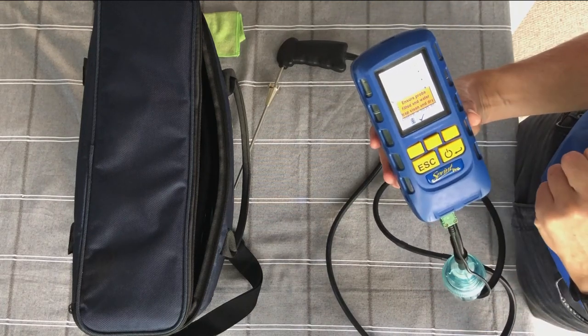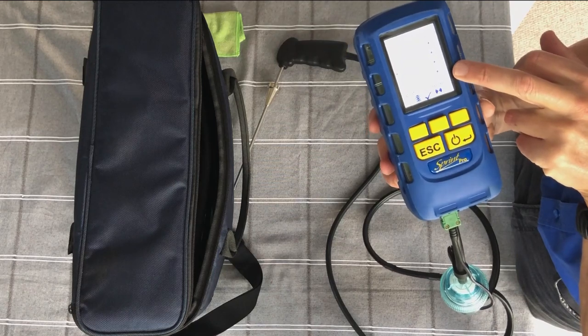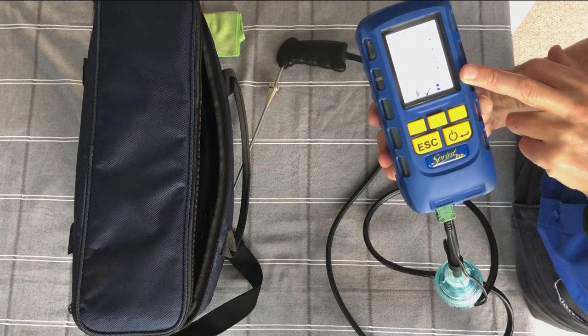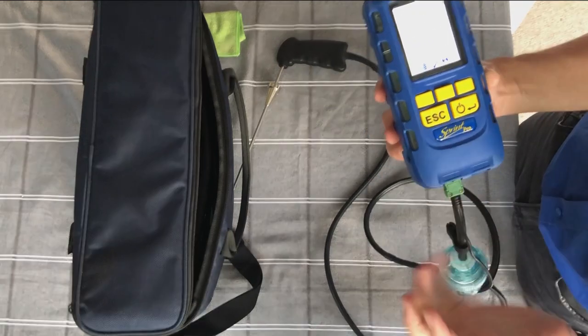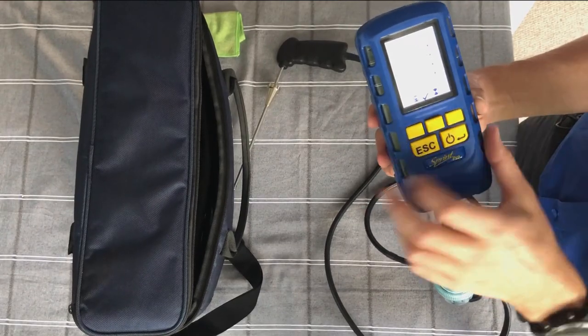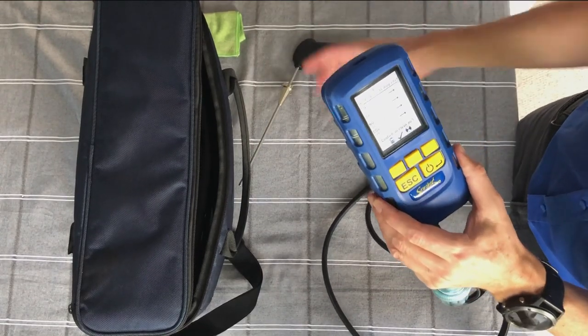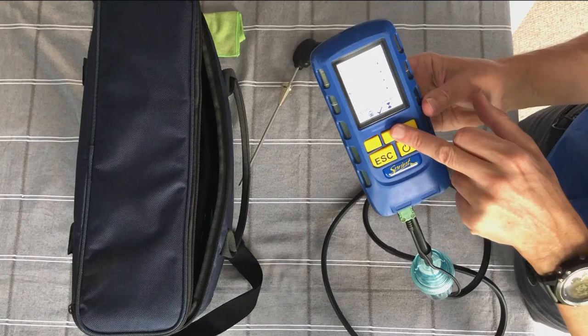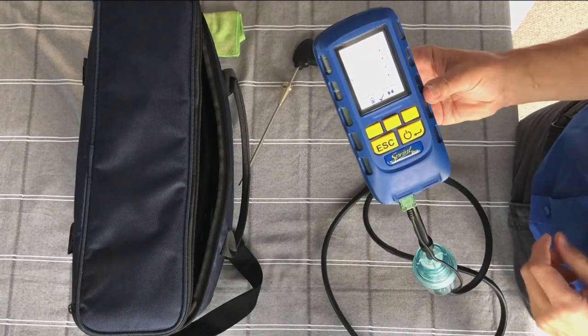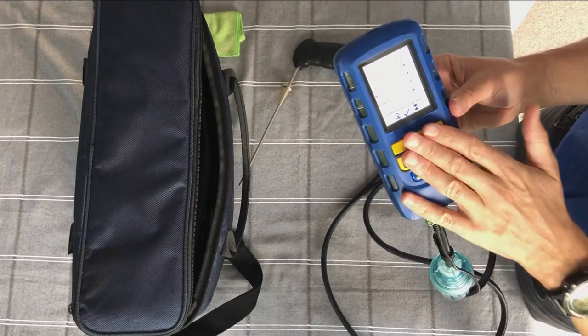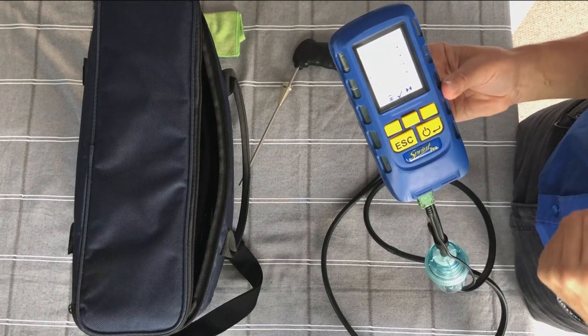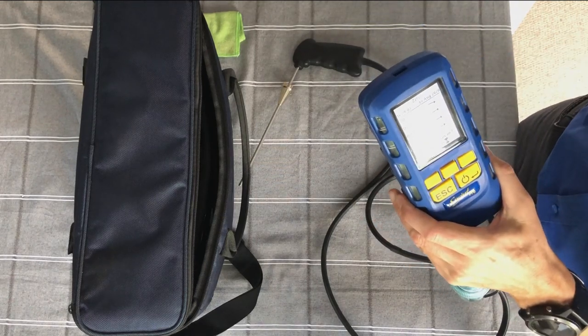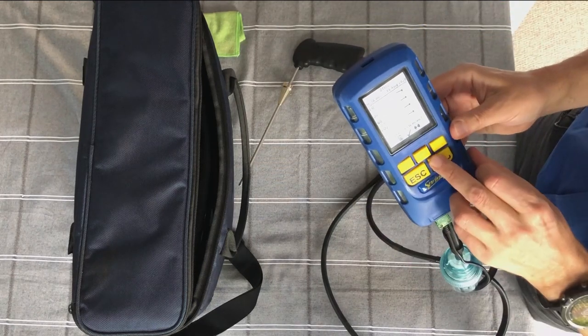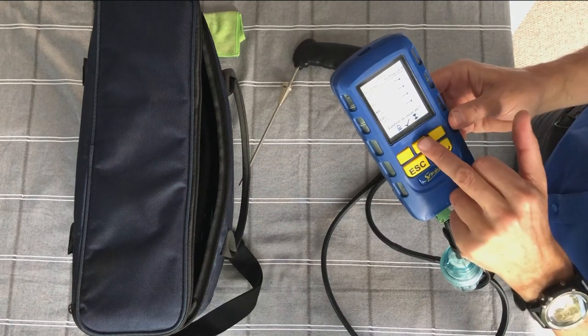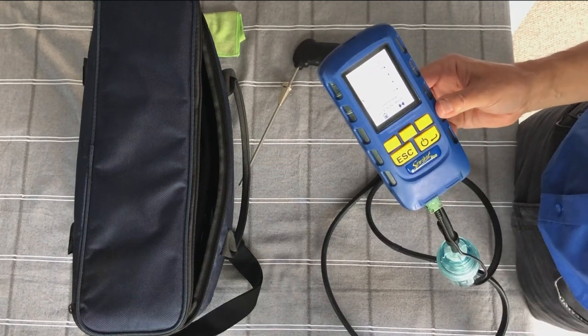So going to flue gas analysis. It says on here, ensure probe fitted and I think water trap empty. So that's just a good thing to do. Confirm I'm in clean air. Obviously I am here. This is just my front room actually, but if you're on site, you don't want to be up close to the boiler when you do this. You want to be either putting your flue probe out the window into fresh air or ideally outside, so you're definitely in clean air. But once you're in clean air, you press the button to confirm you're in clean air.